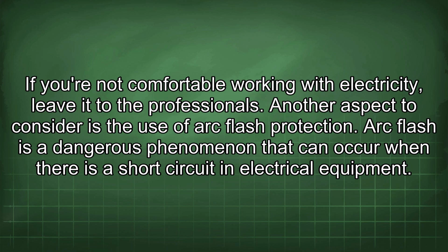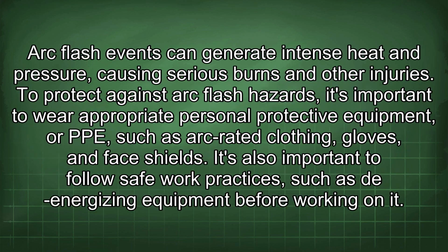Another aspect to consider is the use of arc flash protection. Arc flash is a dangerous phenomenon that can occur when there is a short circuit in electrical equipment. Arc flash events can generate intense heat and pressure, causing serious burns and other injuries. To protect against arc flash hazards, it's important to wear appropriate personal protective equipment, or PPE, such as arc-rated clothing, gloves, and face shields. It's also important to follow safe work practices, such as de-energizing equipment before working on it.